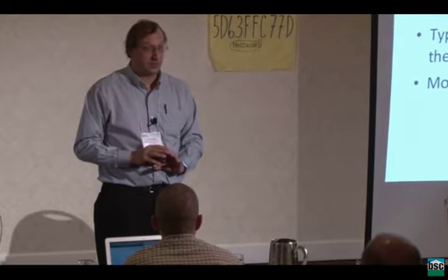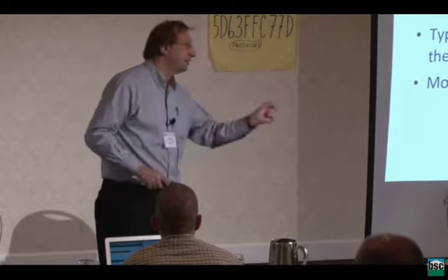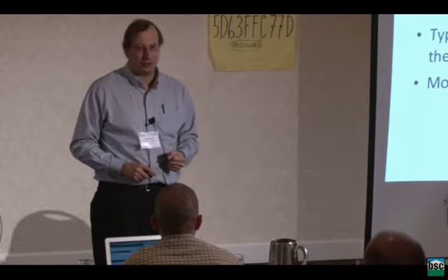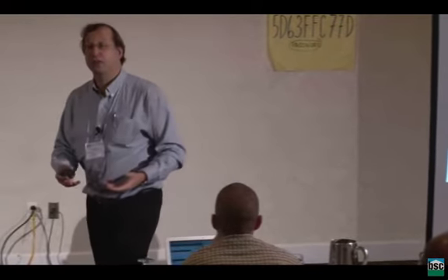The other advantage was that they said, hey, look, if your compressor fails, at least you have heat. And you can just use your toaster. The disadvantage, of course, is that you had to design for really big copper wires and electrical circuits to run this stuff, because running a 9-kilowatt electric heater is something serious. And you needed to size the ductwork to handle the temperature rise that could be created by your 9 kilowatts. So heat pumps were a little bit annoying. They had big ducts, and often in practice in the early days, they spent a lot of time either accidentally or by manufacturer intent running with electric heat as a major proportion of what they did.